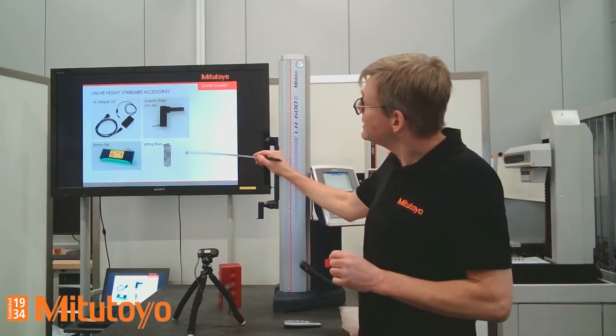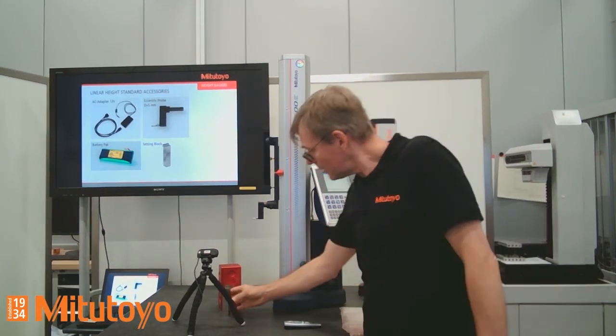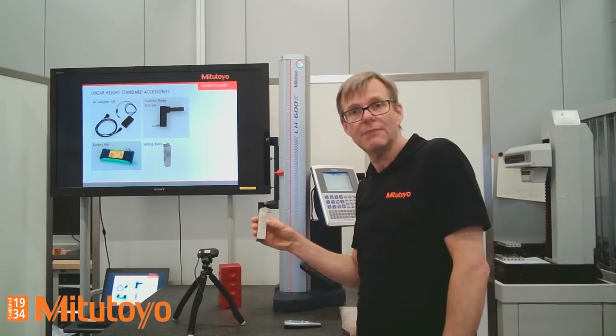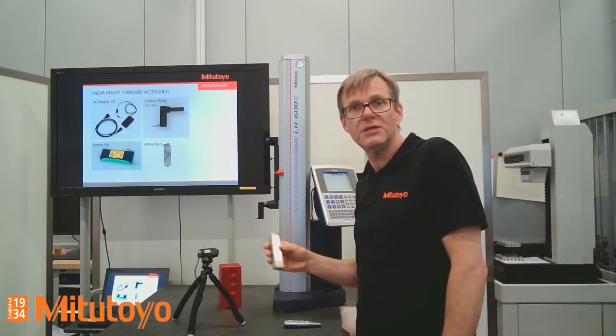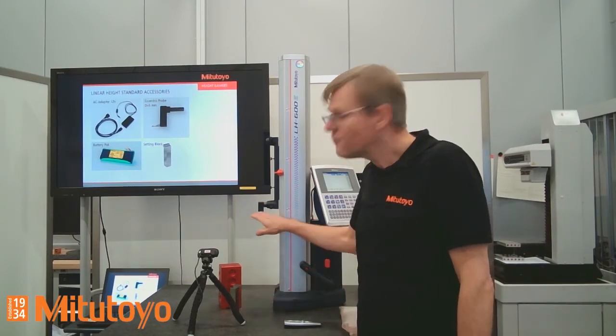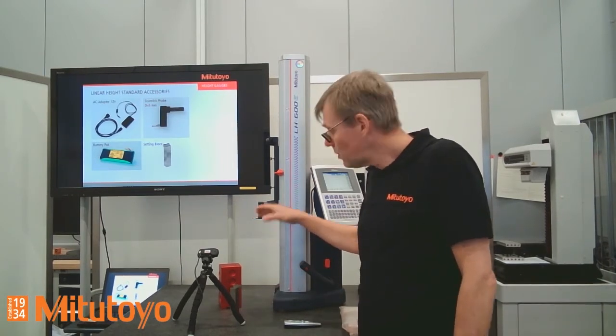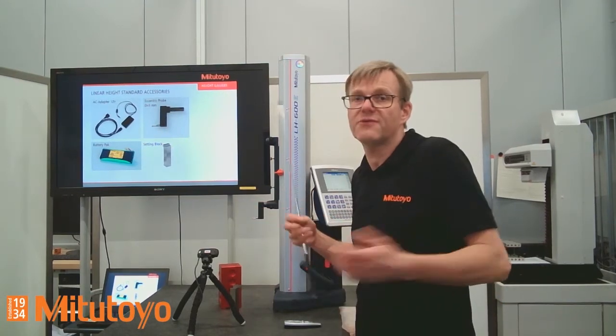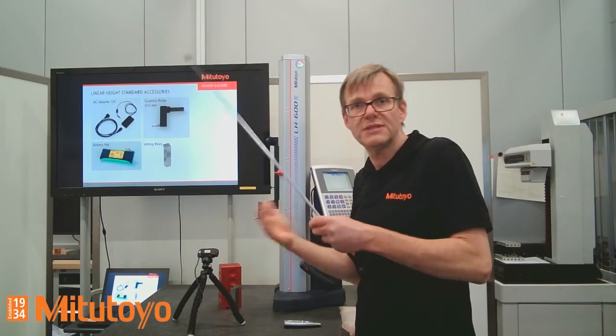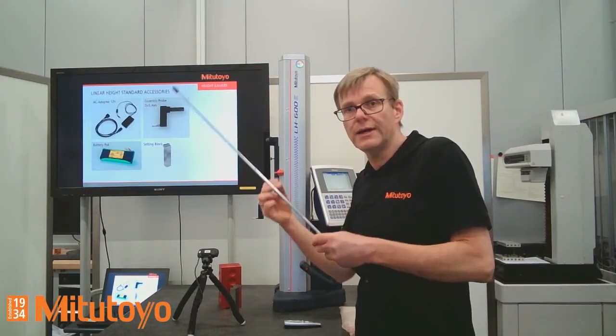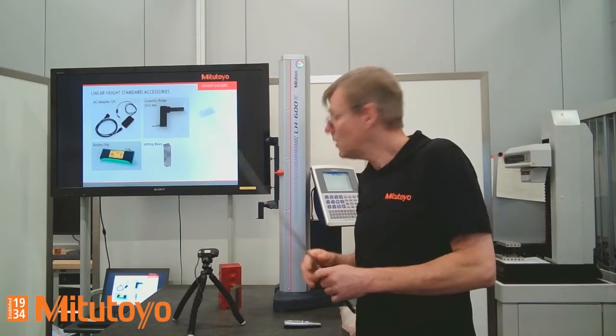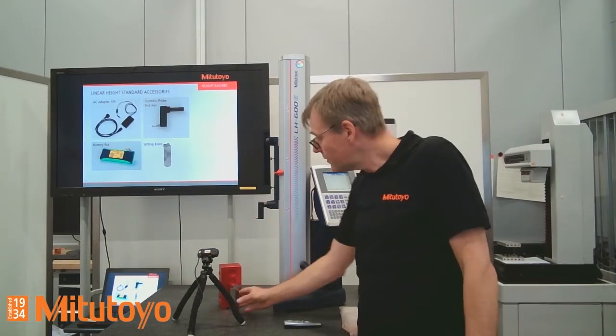We have the setting block, this one here, I'll show you. That's a setting block. This setting block can be used to calibrate the diameter of the probe. I said this one is a 5 millimeter probe, but it's not exactly 5 millimeter. And later on for compensation, we need to know exactly the diameter of this probe. That's why we have the setting block.